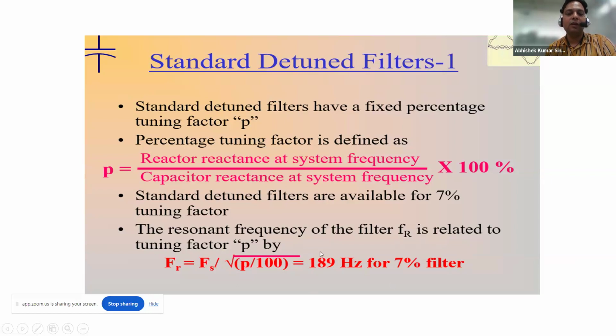That is why we said in the earlier slide that if there is a third harmonic in the system, this will not cater to it, because it can only cater to harmonics at 189 hertz or above. For the third harmonic, that means 150 hertz, we have to plan a 14% filter, which is able to cater to 134 hertz. Any frequency which is 134 hertz or more can be suppressed by a 14% detuned filter.